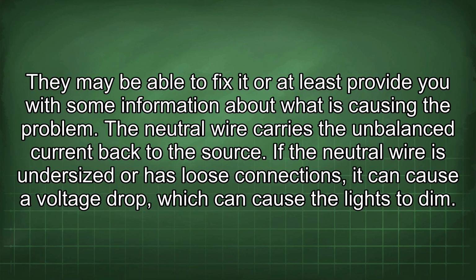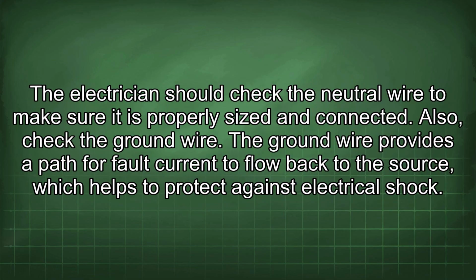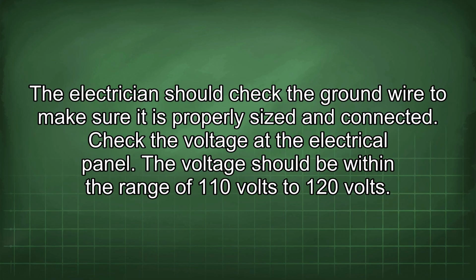The neutral wire carries the unbalanced current back to the source. If the neutral wire is undersized or has loose connections, it can cause a voltage drop, which can cause the lights to dim. The electrician should check the neutral wire to make sure it is properly sized and connected. Also check the ground wire. The ground wire provides a path for fault current to flow back to the source, which helps to protect against electrical shock. The electrician should check the ground wire to make sure it is properly sized and connected.